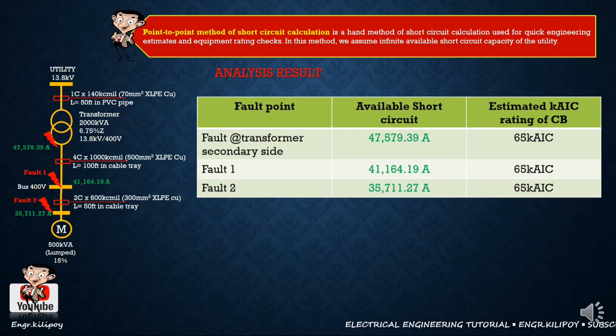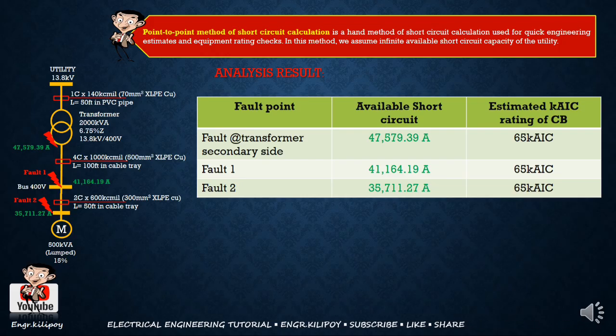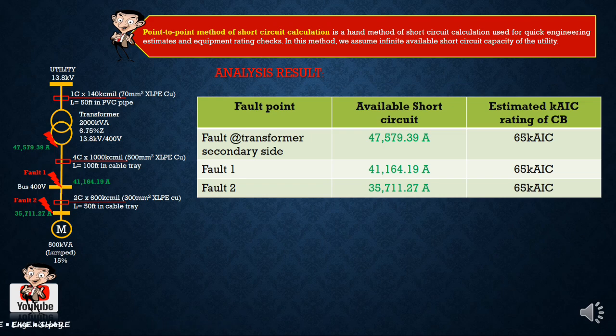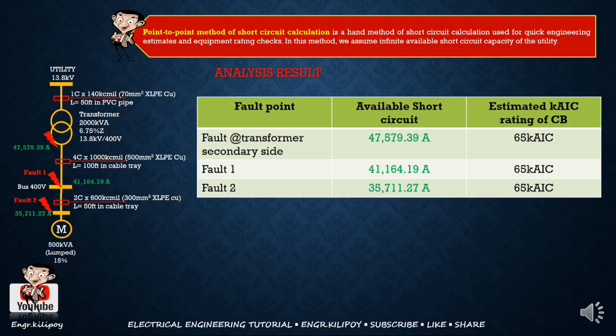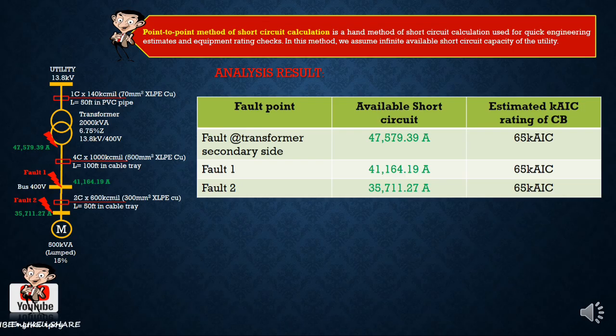So, yung analysis result using the point-to-point short circuit calculation, yung fault at transformer secondary side kapag nagka-fault doon sa point na yon, meron tayong 47.6 kiloampere, 41.2 kiloampere sa fault 1, at sa fault point 2 meron tayong 35,711 ampere. So, magkakaroon tayo ng estimate dyan ng AIC rating ng CB, which is 65 kAIC. All 65 kAIC yung magiging initial estimation mo, just in case nga nagkaroon ng ganong sinabi ko kanina, yung sumabog yung breaker. So, i-compare mo siya 65 kAIC initially.